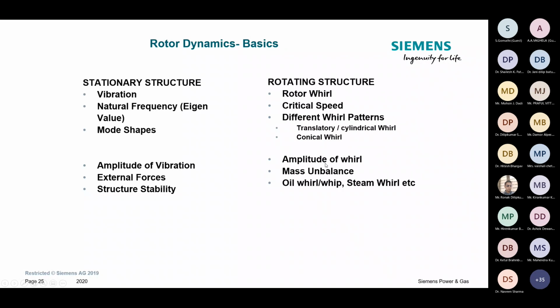Then the amplitude of vibrations. The amplitude of the whirl is important, and we measure it through probes, along with mass unbalance. Normally the external forces which excite the system are balanced, but there are other forces also, like oil whirl, whip, steam whirl, and those things.